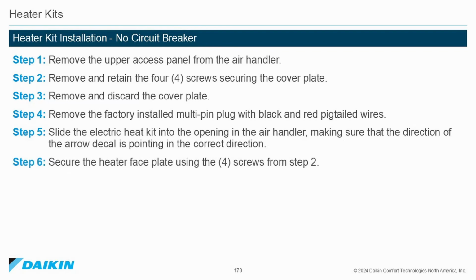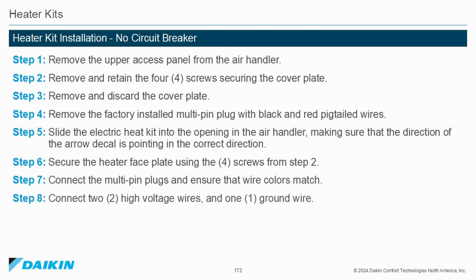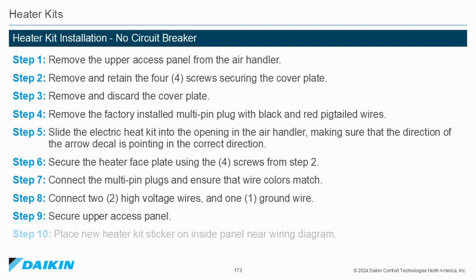Step 6. Secure the heater face plate using the 4 screws from Step 2. Step 7. Connect the multi-pin plug and ensure that the wire colors match. Step 8. Connect 2 high-voltage wires and 1 ground wire. Step 9. Secure the upper access panel. Step 10. Place the new heater kit sticker on the inside panel near the wiring diagram.